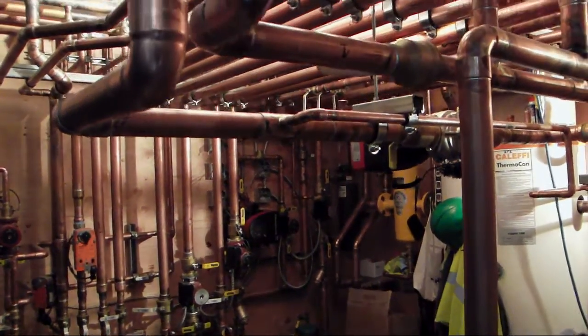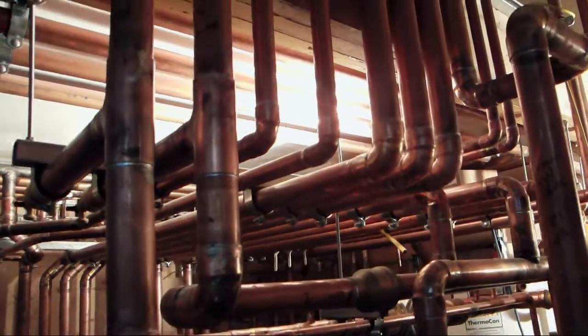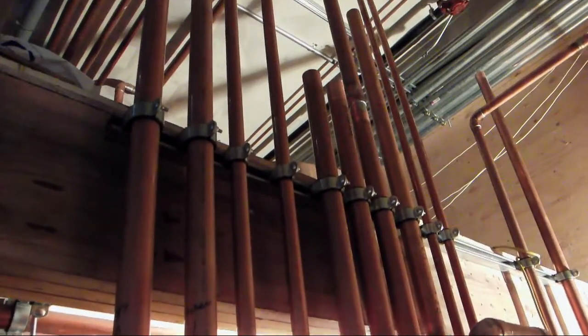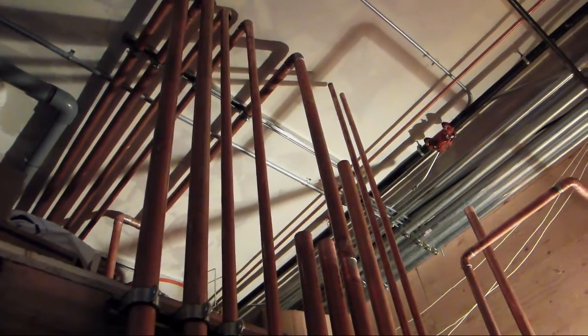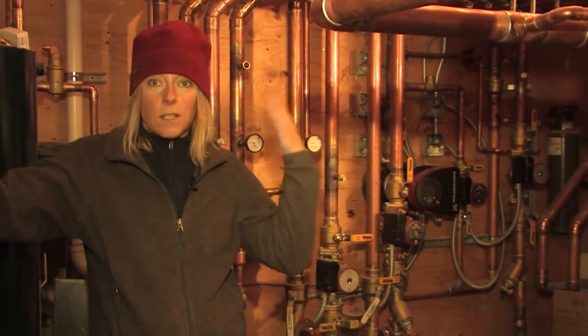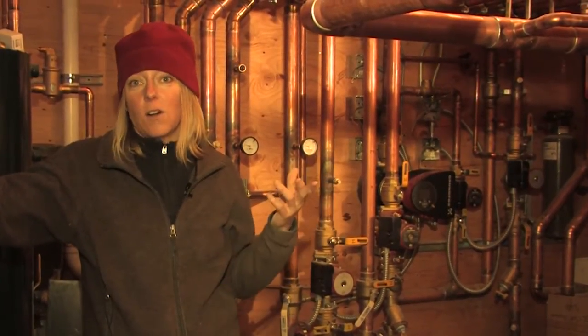When the water goes into the condenser, it goes in at pretty much ambient temperature, anywhere between 55 and 70 degrees. By cooling the condenser coil, it takes all the heat off of that coil, and the water comes out anywhere between 90 and 105 degrees.